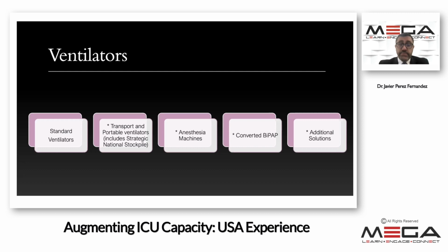But then we have the transport and portable ventilators, and I'd say these are something that includes a strategic national stockpile. Then some individual says, well, if we don't have more ventilators, we're going to use anesthesia machines. Now, anesthesia machines are complicated to use as a ventilator for ICU. They require adapting the machine to the ICU. They cannot be used just as simply as that.